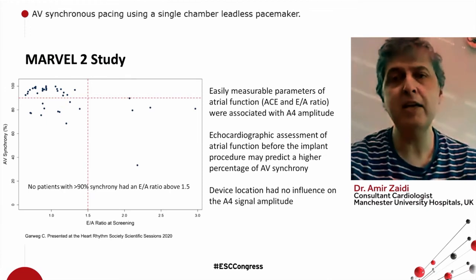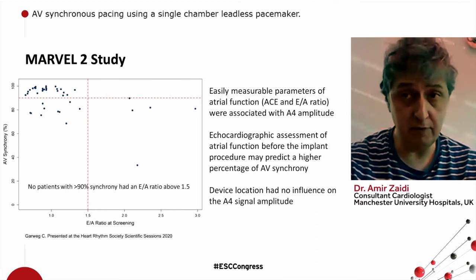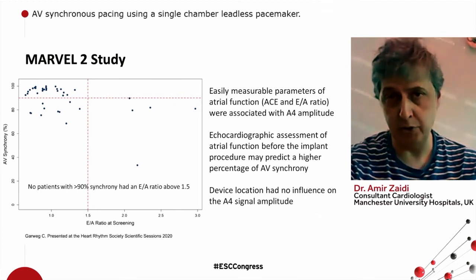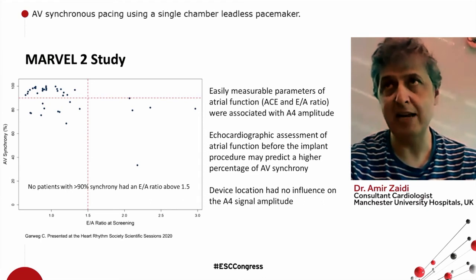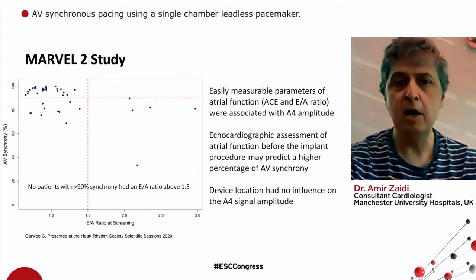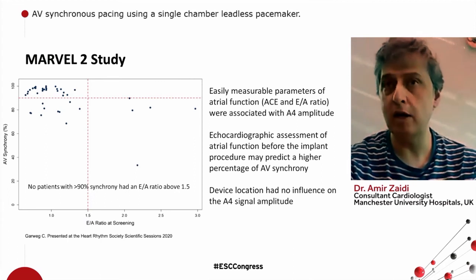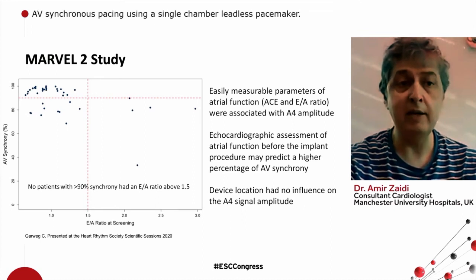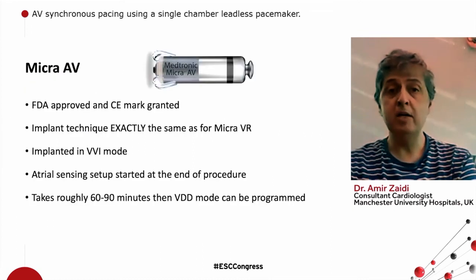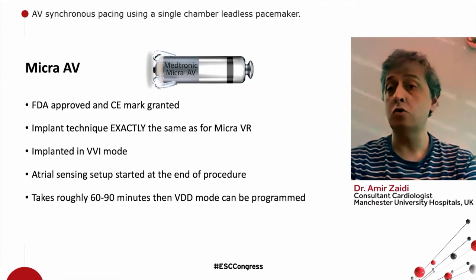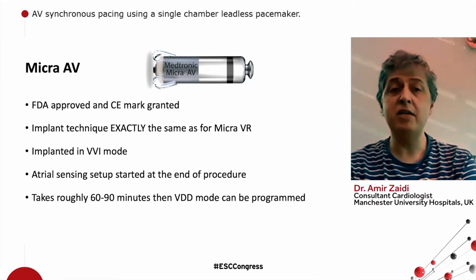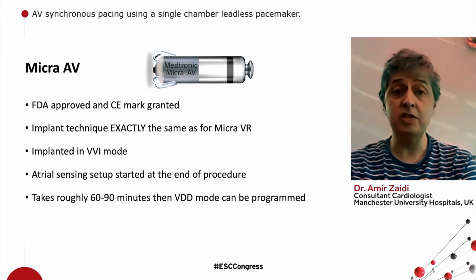And the other thing that was important is the position of the device had no real influence on the A4 signal amplitude. So in terms of implant technique, it's exactly the same as for Micra VR, and the placement of the device does not affect the efficacy of the AV synchrony algorithm. So Micra AV has worked well in studies. It now has FDA approval and CE mark.